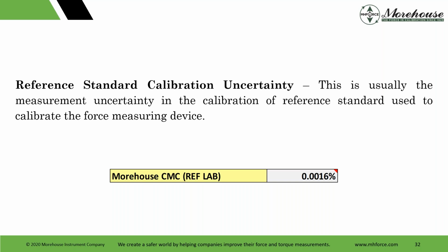And then reference standard calibration uncertainty, usually the measurement uncertainty of the reference standard used. If we're using dead weights, great. Our dead weight machine, as I said, is calibrated directly by NIST. We have a realized uncertainty of about 0.0016%.